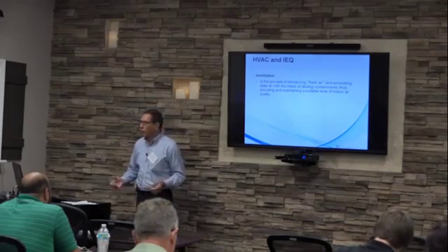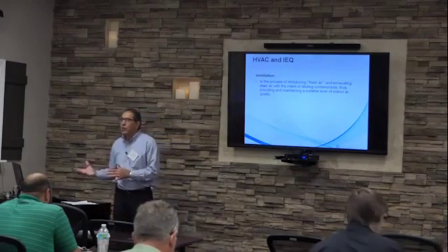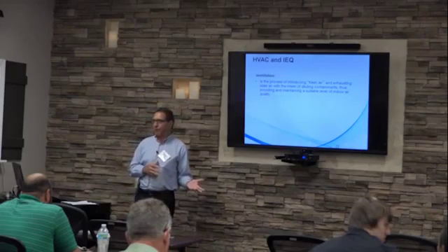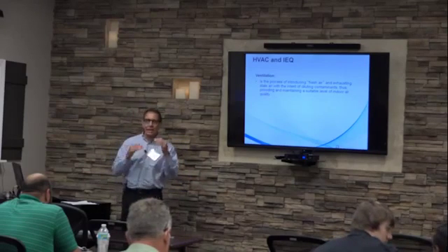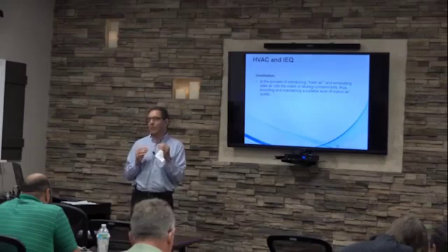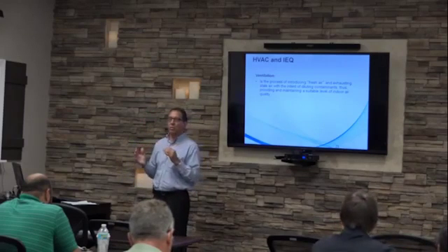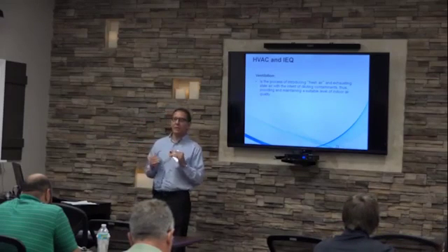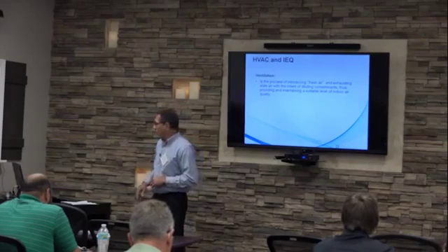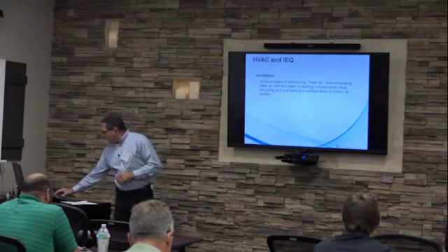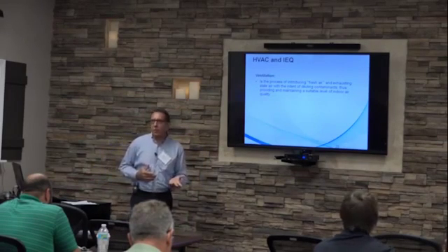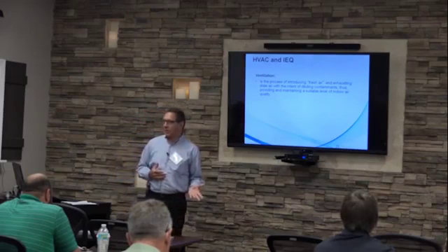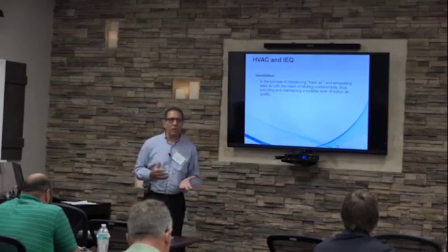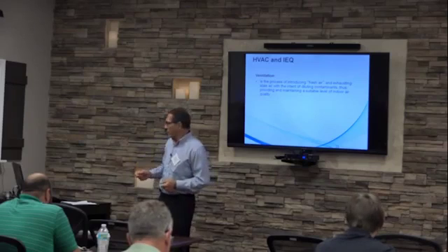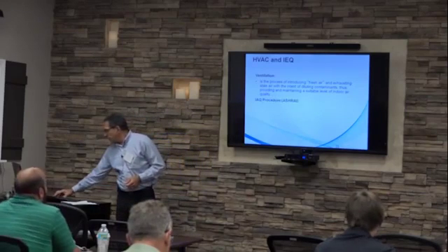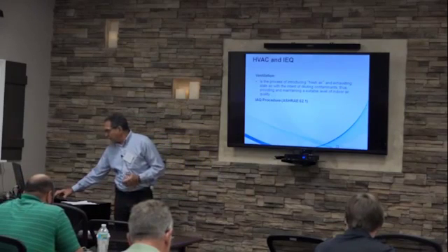If we're talking about HVAC, we need to talk about ventilation. Ventilation is used for introducing fresh air and exhausting stale air. Okay, it needs to be done in a controlled manner. Bringing outside air through uncontrolled pathways is really not a good idea. So the intent of ventilation is for diluting contaminants that are present in the air. And that's the only reason that we bring fresh air into a building.